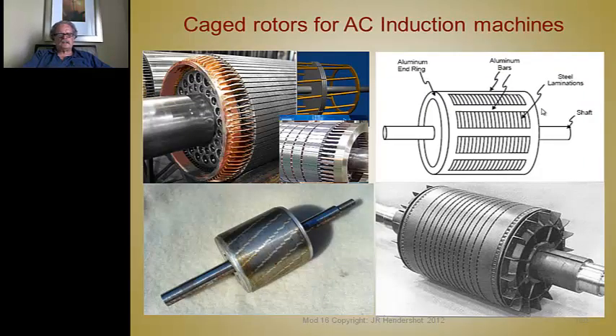Here's a picture of some more cage rotors, and I think it's important to go over these. Here's an aluminum one with bars extended past the length of the core, and there's vent passageways through the core. Here's another very strange looking rotor construction. Here's your flat rectangular bars that go down the slot, and they're somehow attached to a ring of copper here to make a squirrel cage. This is another example of a fabricated rotor with cooling vent passages through it, and the bars are spaced out past the end ring, and this has a cooling fan added to the end of it.